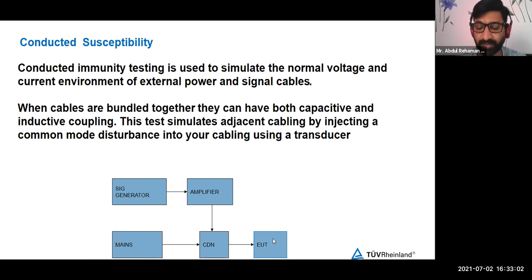Here, when we are testing on the mains, the noise which is coming from the mains gets filtered before going to the EUT, and also when we are injecting the noise through our signal generator, it should not couple to the mains. So that's the reason why this coupling decoupling network is used in between, and it is also used to inject the noise onto the EUT. So different levels are defined in the standard.